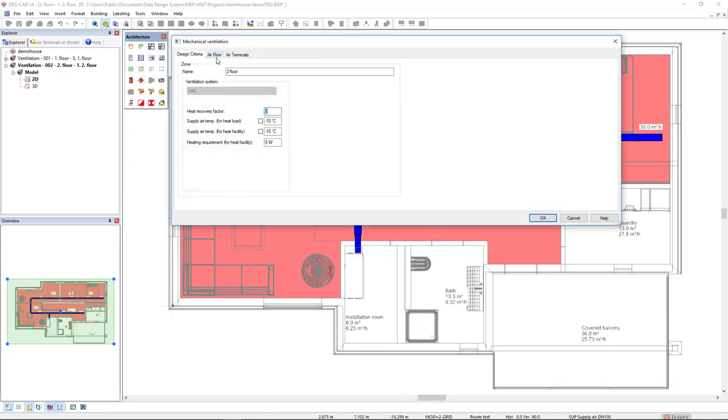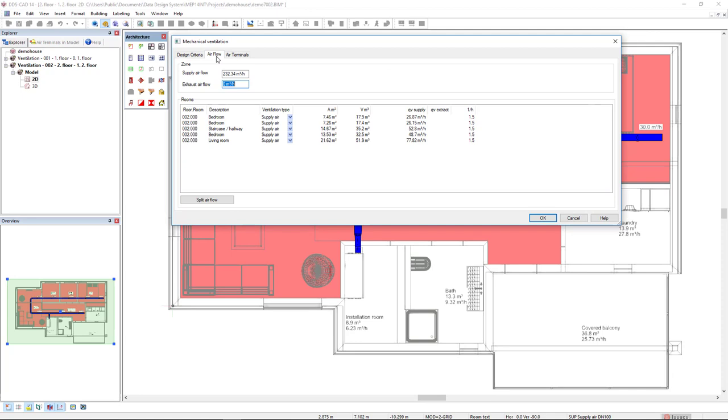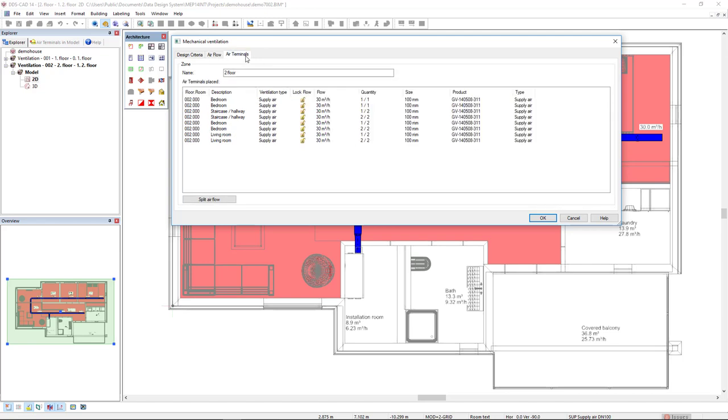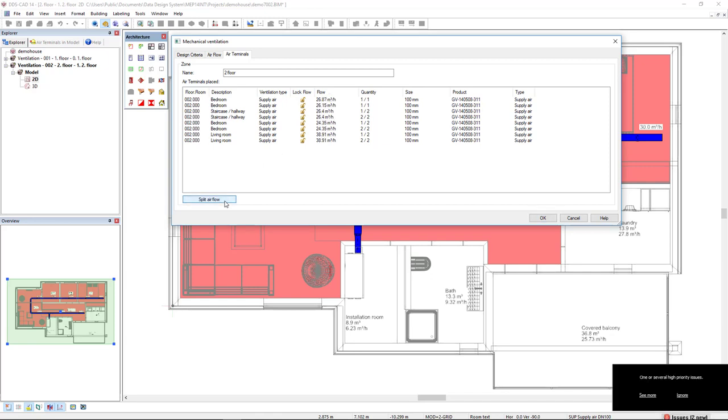In the tab airflow, we see here the volume and the required airflow for each room. And here the exchange rate. In the tab air terminals, we see all the air terminals that have been inserted with the predefined flow. Click split airflow. And the air terminals are calculated from the required flow.